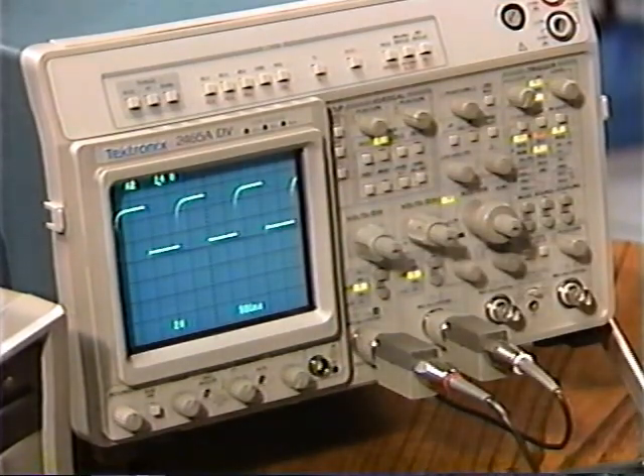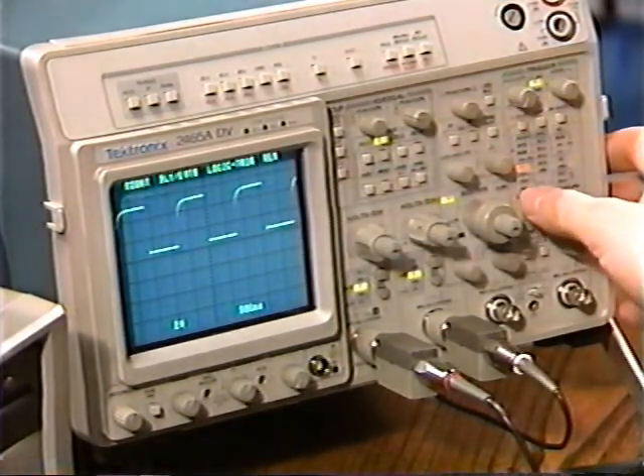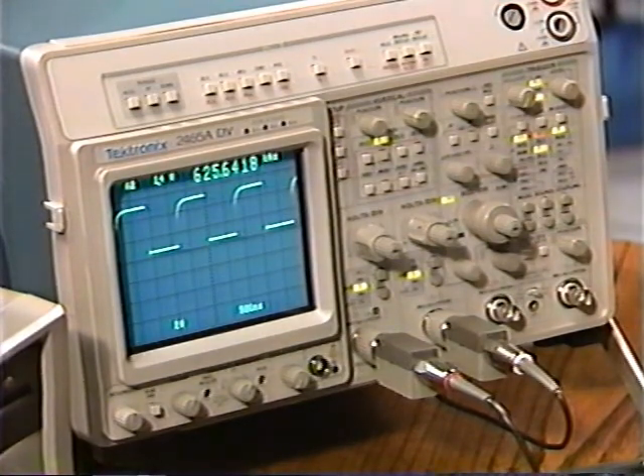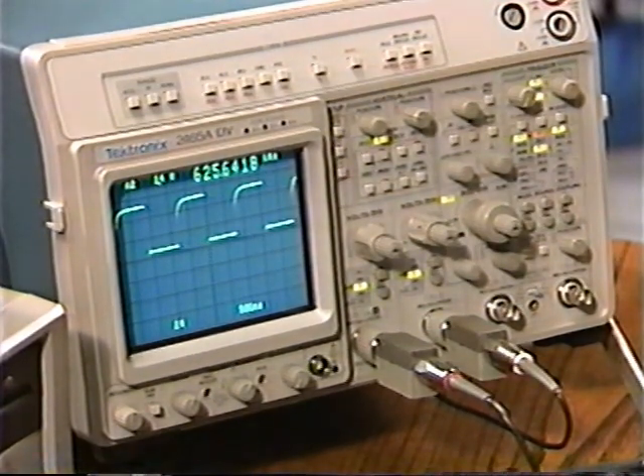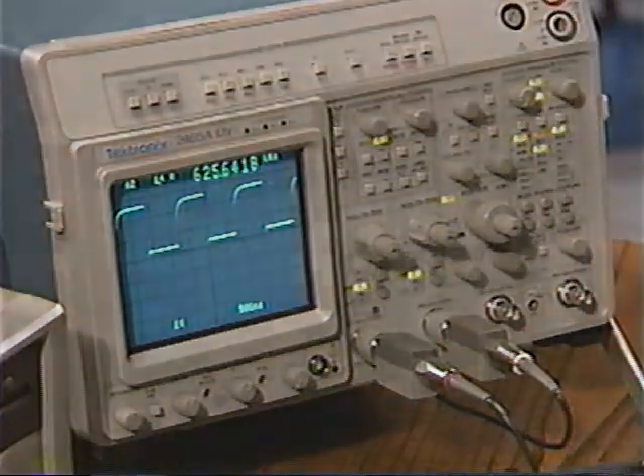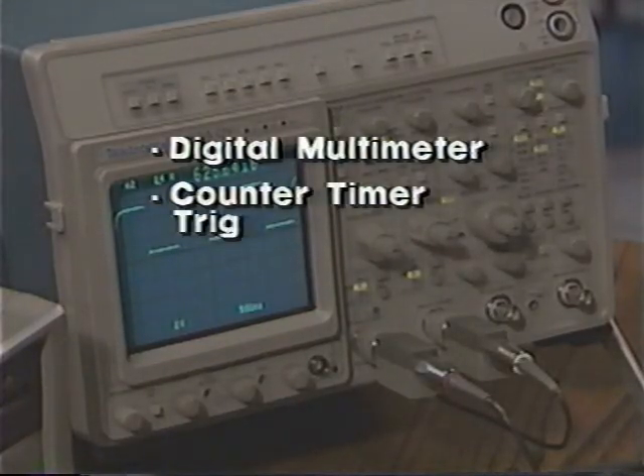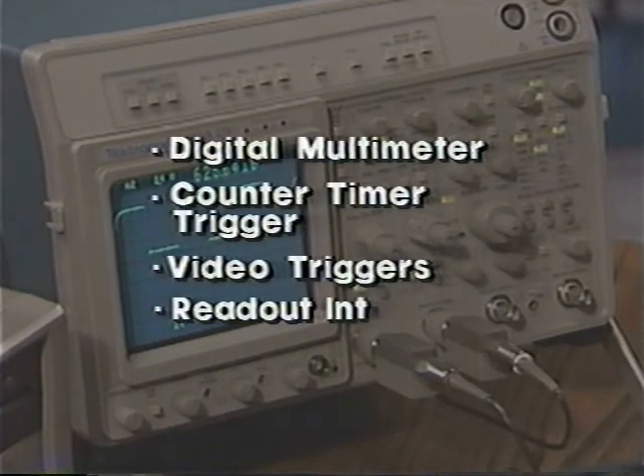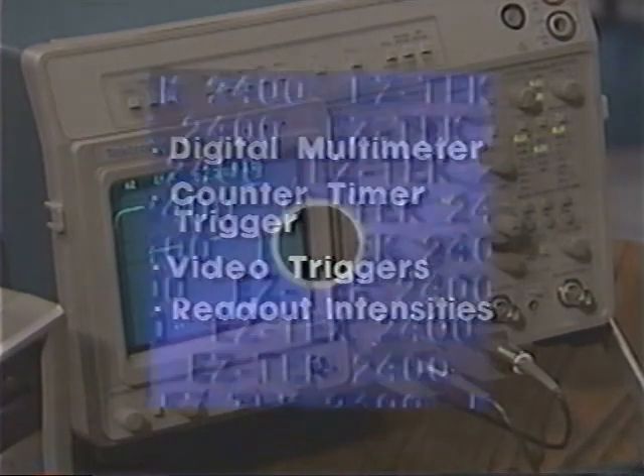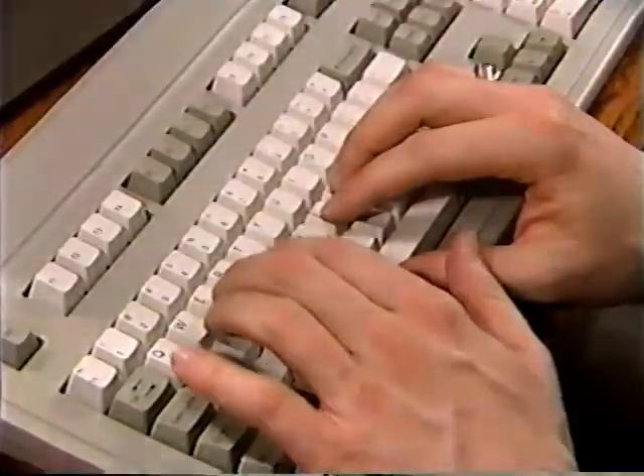Next, EZtech prompts us to set up the scope to make the measurement. Connect the probe. Then press Auto Setup and turn on the counter. EZtech then stores the entire front panel setup of your scope. That's right, actual knob and switch settings, the digital multimeter, the counter timer trigger, the video triggers, and even the display and readout intensities are all stored on a disk. When the procedure is replayed, the scope is automatically set up. The operator doesn't waste time turning knobs or pushing buttons.